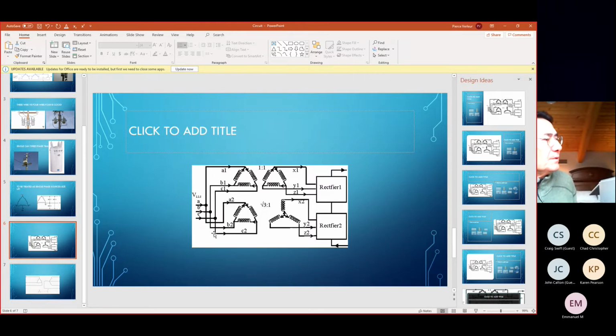You have a 3-phase line input into what amounts to 2 3-phase outputs, one into one rectifier, one into another, and the resultant DC bus to the capacitors of the drive. What they in essence do is they shift the 3-phase output between the 2 secondary windings anywhere from 5 to 15 degrees.